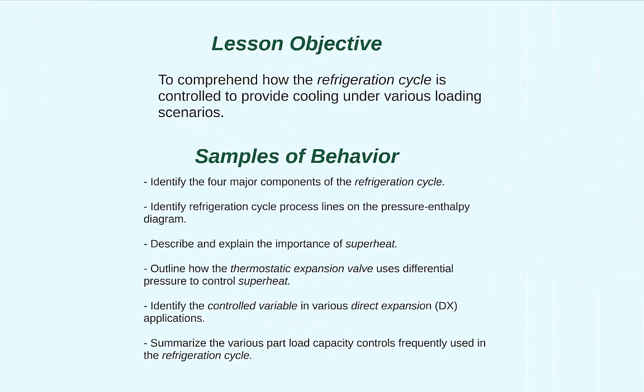The objective for this lesson was for students to comprehend how the refrigeration cycle is controlled to provide cooling under various loading scenarios. The corresponding samples of behavior were: identify the four major components of the refrigeration cycle, identify refrigeration cycle process lines on the pressure enthalpy diagram, describe and explain the importance of superheat, outline how the thermostatic expansion valve uses differential pressure to control superheat, identify the controlled variable in various direct expansion applications, summarize the various part load capacity controls frequently used in the refrigeration cycle.